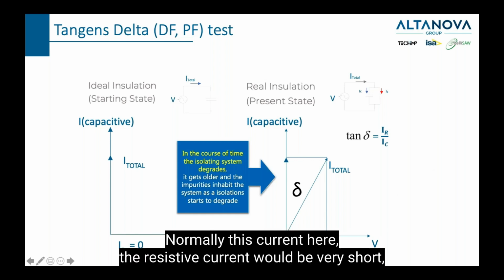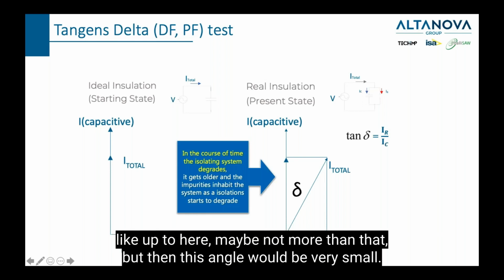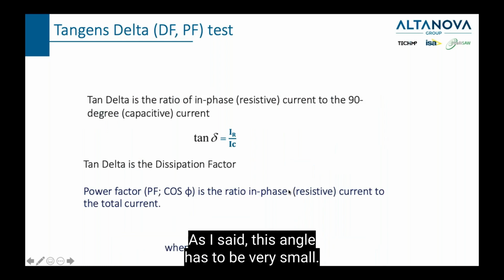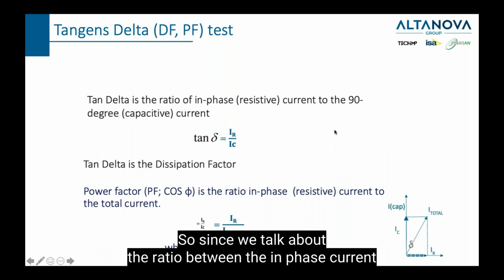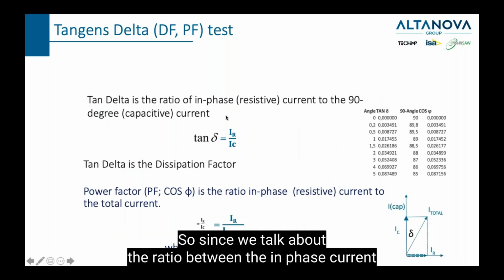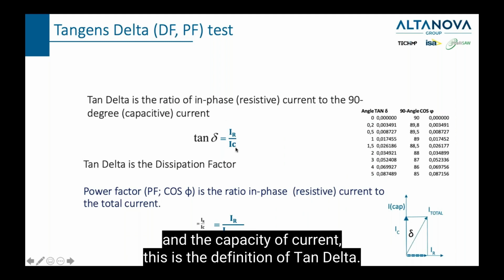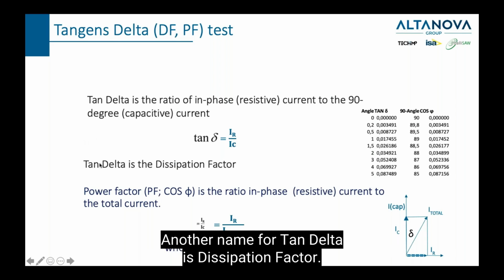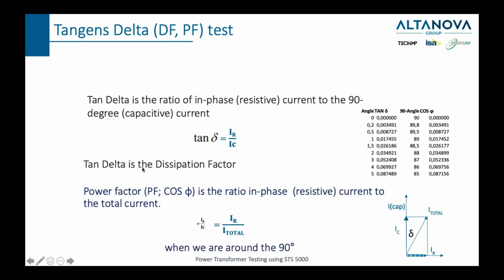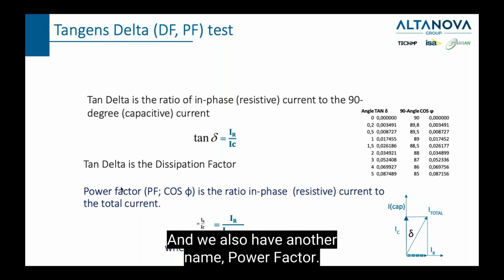Normally, this current here, the resistive current, will be very short, like up to here, maybe not more than that. But then this angle would be very small. As I said, this angle has to be very small. Since we talk about the ratio between the in-phase current and the capacitive current, this is the definition of tan delta. Another name for tan delta is dissipation factor, and we also have another name, power factor.